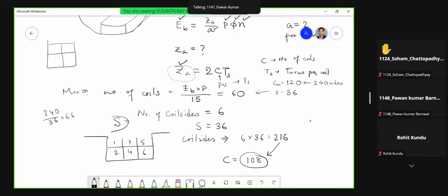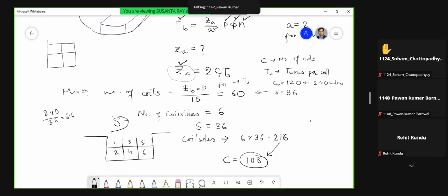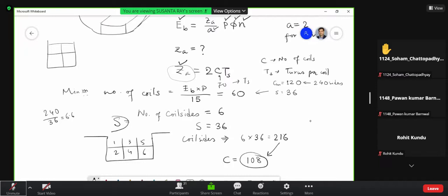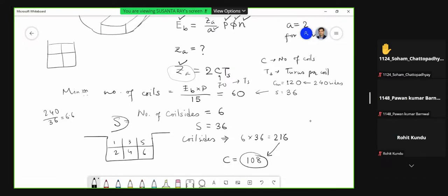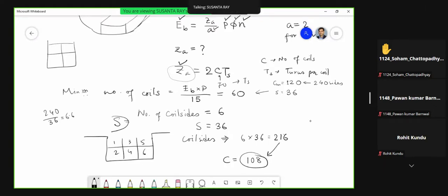Sir, actually, I have finally found the number of coils as 90, but earlier I had assumed 97. So I have to change my number of conductors according to 90 coils. It should not deviate from your actual number of conductors too much. You have to adjust somewhere else.